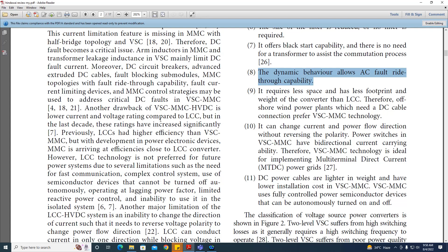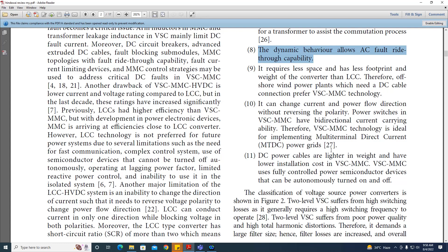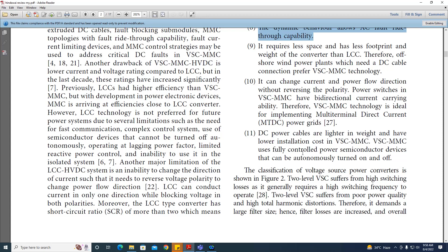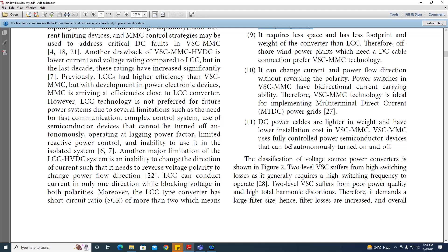Therefore, offshore wind power plants which need a DC cable connection prefer VSC MMC technology. It can change current and power flow direction without reversing the polarity. Power switches in VSC MMC have bidirectional current carrying capability. Therefore, VSC MMC technology is ideal for implementing multi-terminal direct current MTDC power grids. So, in case of MTDC applications, VSC MMC are preferred. DC power cables are lighter in weight, and we have lower installation cost in MMC VSC. VSC MMC use fully controlled power semiconductor devices that can be autonomously turned on and off.